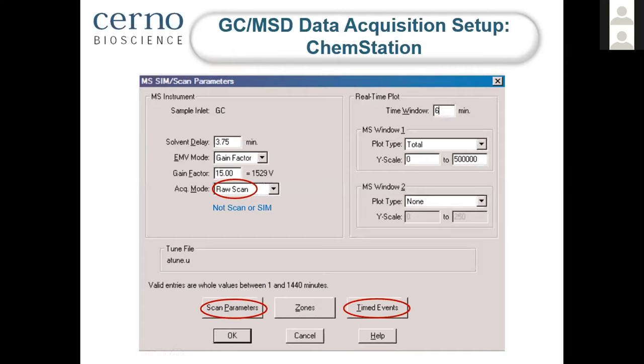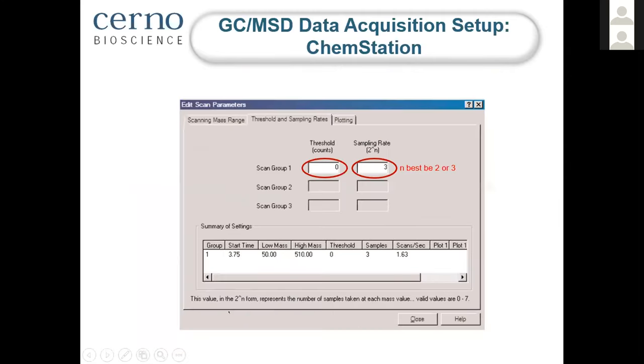We do require some special setup in order to acquire the kind of data for MassWorks. The setup is slightly different depending on the system you use and the data acquisition software. For the traditional GC-MSD with the ChemStation, for example, the setup would involve changing a couple of mass spec acquisition method parameters, including the acquisition mode. For the ChemStation, the terminology is raw scan. You have to acquire in the raw scan mode, not the scan or SIM mode. And then you want to change the scan parameters to set the threshold to zero so that we don't miss any data.